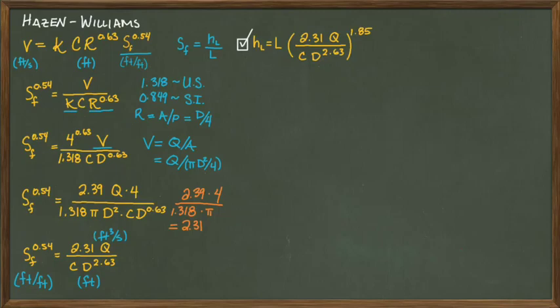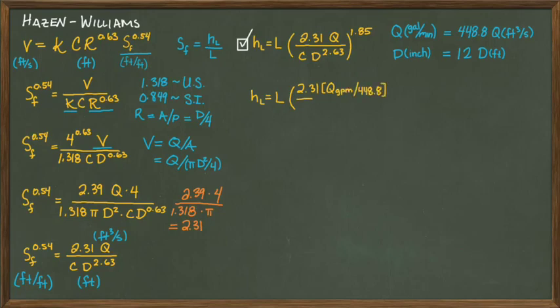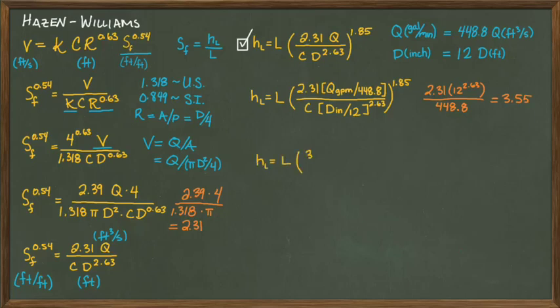To further make this equation easier to use, we need the flow rate to be in gallons per minute and the diameter in inches because those are the typical units used in water systems in the United States. Substituting those conversion values into our equation and then combining these constants once again provides us with a new equation where the conversion constant changes from 2.31 to 3.55. And that allows us to use the flow rate in GPM and the diameter in inches.